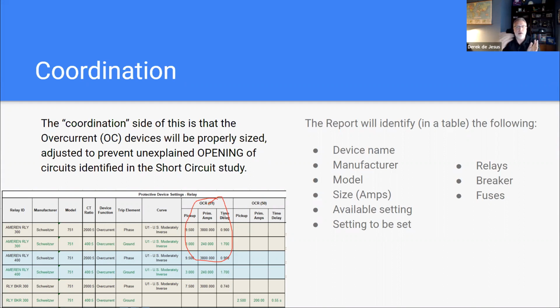800 amp frame, 800 amp trip, or 800 amp frame, 400 amp trip. You can also do the same thing with an 800 amp frame breaker by dialing down those settings. So if you wanted to trip at 400 amps, you would change that long time value to whatever the value is for that breaker, 0.5.